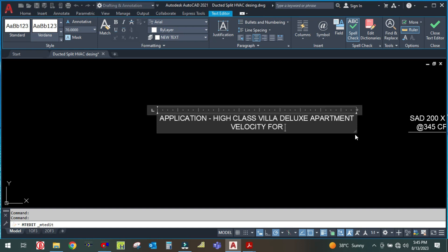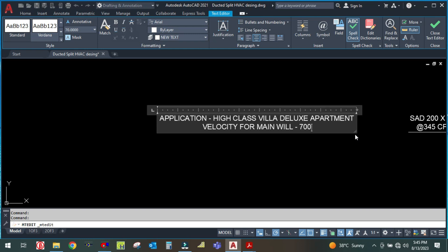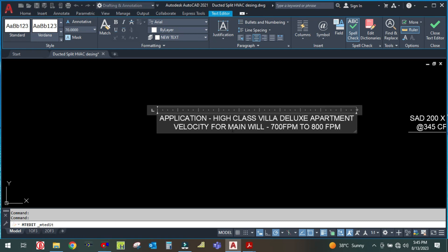For the main duct, the velocity will be 700 to 800 feet per minute, and this will be fixed throughout the main duct.